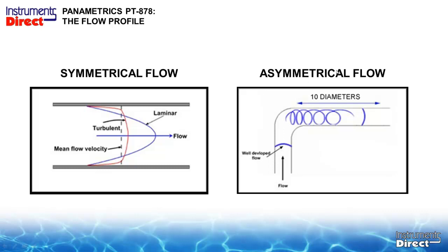The picture to the right is an asymmetrical flow profile. And this is basically what happens when you don't have enough straight run of pipe. So flow going up the elbow here, you notice there's a shorter distance on the inside, a longer distance on the outside. The flow will tumble inside the pipe there, and right after the elbow you will get a lot of disruption. So if you were to put your ultrasonic transit time meter right there, you probably wouldn't get a very good flow rate. In fact, you'd probably get a fault condition. You wouldn't get anything at all. You're supposed to move downstream 10 pipe diameters, put your sensor there, because then down there it'll look like a symmetrical flow profile.